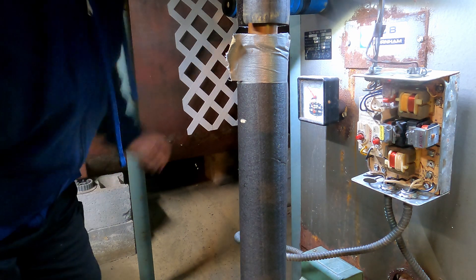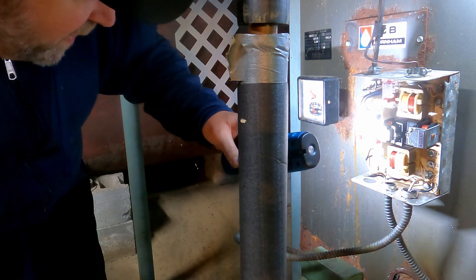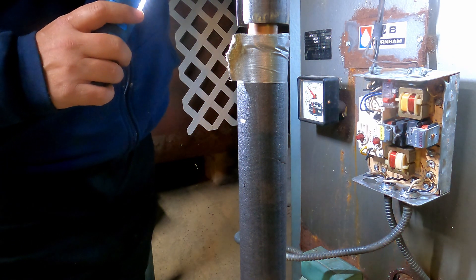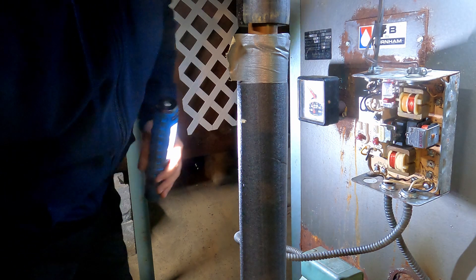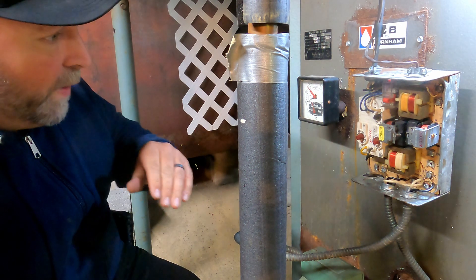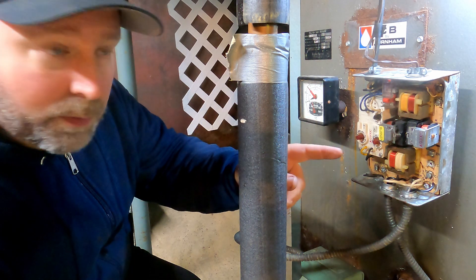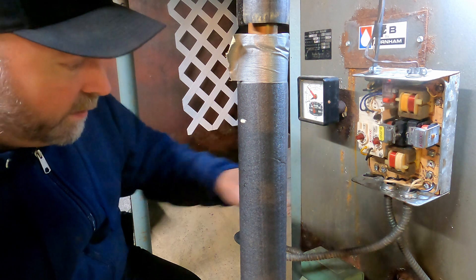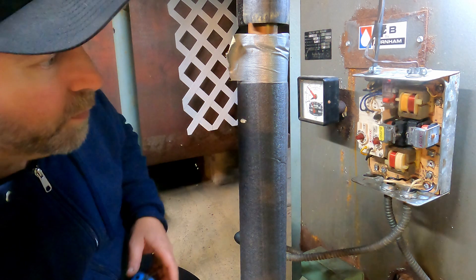Alright YouTube, you're going to find out when I do if this is going to work or not. I'm going to flip the switch on — I have all my settings copied from the one I just took off — and we will see if we have fire. Fired right up, so that's good. Now we just have to wait and see when it gets up to temperature if the other contact will open up. This one here is marked burner, and that one there is for the circulator pump — so when it gets up to minimum temperature the circulator pump contact should trip.